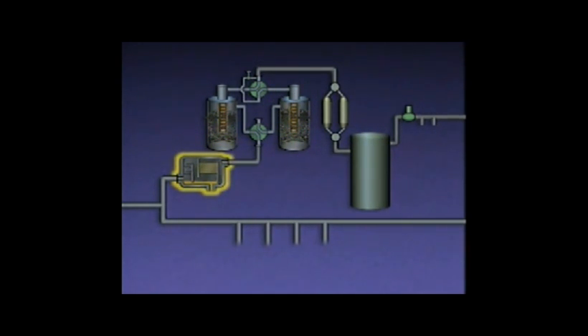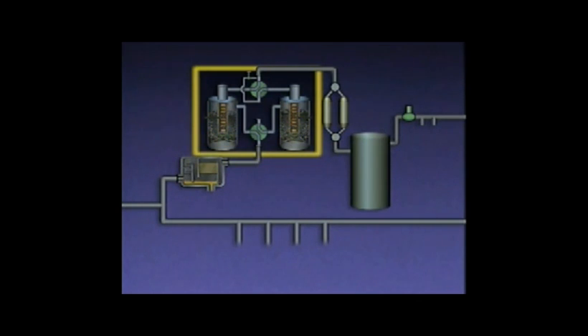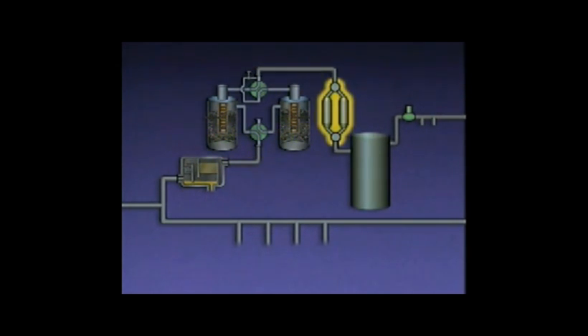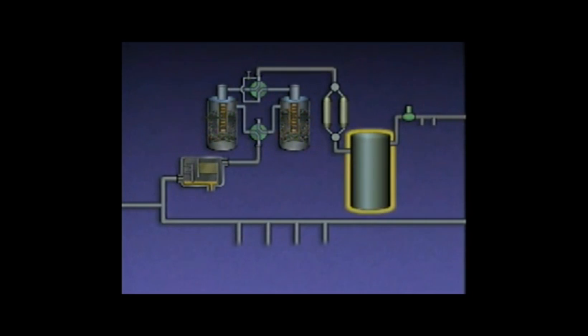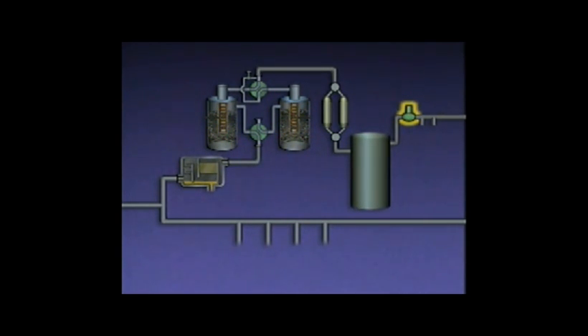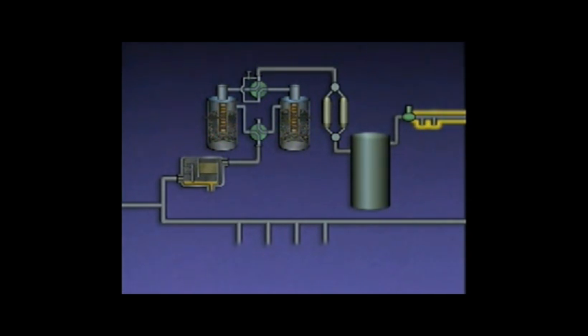The oil that is removed collects in the bottom of the separator and is often drained to a waste system. A desiccant dryer removes moisture that may be present in the air, and filters remove any solid impurities. Dry filtered air suitable for use in a control system is typically stored in a receiver until needed, then sent to a pressure reducing valve. The valve reduces the 120 PSI air to 50 PSI for use in pneumatic instruments and devices throughout the plant. The compressed air from the pressure reducing valve is distributed by an instrument air header, which supplies 50 PSI air for use in pneumatic control systems. This pressure can be further reduced by devices that receive compressed air from this header.